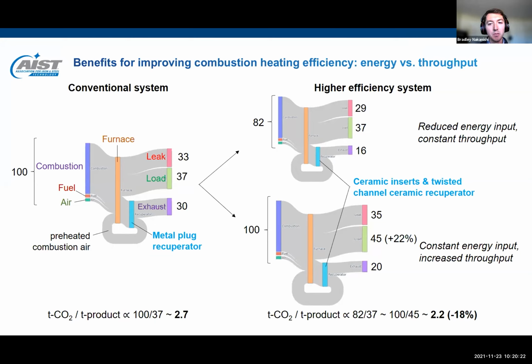You can also see the heat flowing to the load, that is the steel strip, the exhaust, and furnace leaks. The right diagrams show two extremes for the same system, now utilizing high efficiency ceramic inserts and recuperators. The top furnace operates at similar throughput to the system on the left, but here 18% energy savings are obtained. Similarly, the bottom furnace operates at the same energy input while adding 22% throughput.